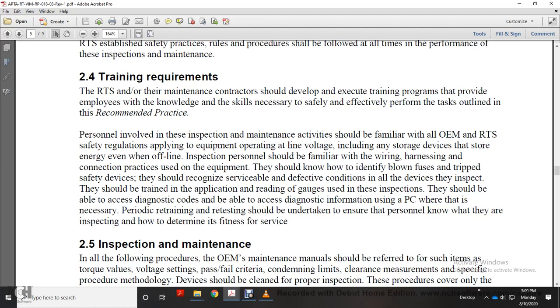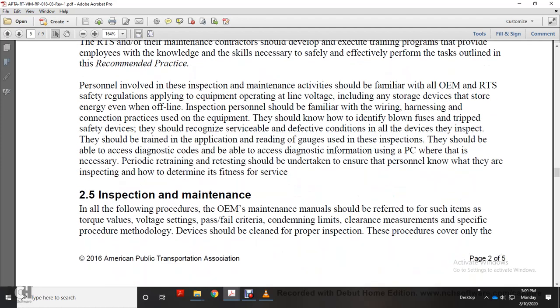Even with offline inspection, personnel should be familiar with wiring harness connection processes and practices used within the equipment. They should know how to identify a blown fuse and tripped safety devices. They should recognize serviceability device conditions. All device inspectors should be trained in the application regarding reading gauges used in the inspection. They should be able to access diagnostic codes and diagnostic information using a PC where necessary.